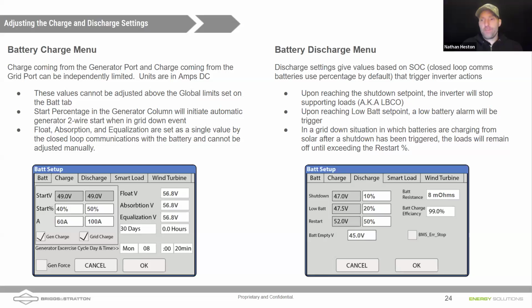The low battery, which should be higher than shutdown, is when you're going to get an alarm indicating that you're near a low battery cutout point. And then the restart is the point at which, if it does go to a shutdown, it's not necessarily going to turn back on right away. You want the batteries to be able to be recharged up to maybe 50% and then allow the inverter to come back on when it knows it has some reserve there as well. And these are settable values. I would just point out to people that because we're showing 10%, 20%, and 50%, that doesn't mean we're recommending those. In fact, on the battery empty voltage, I recommend 48 volts here.